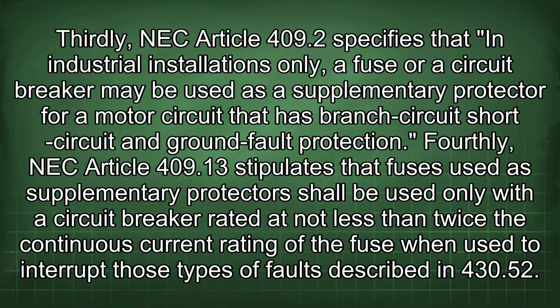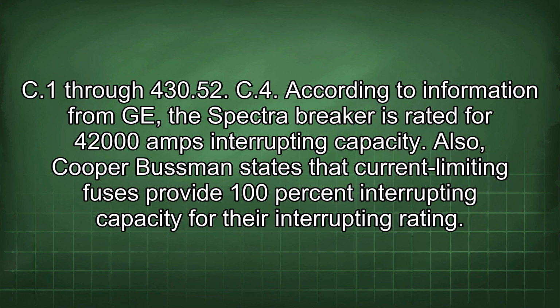Fourthly, NEC Article 409.13 stipulates that fuses used as supplementary protectors shall be used only with a circuit breaker rated at not less than twice the continuous current rating of the fuse when used to interrupt those types of faults described in 430.52. C.1 through 430.52 C.4. According to information from GE, the Spectra breaker is rated for 42,000 amps interrupting capacity. Also, Cooper-Bussmann states that current-limiting fuses provide 100% interrupting capacity for their interrupting rating.